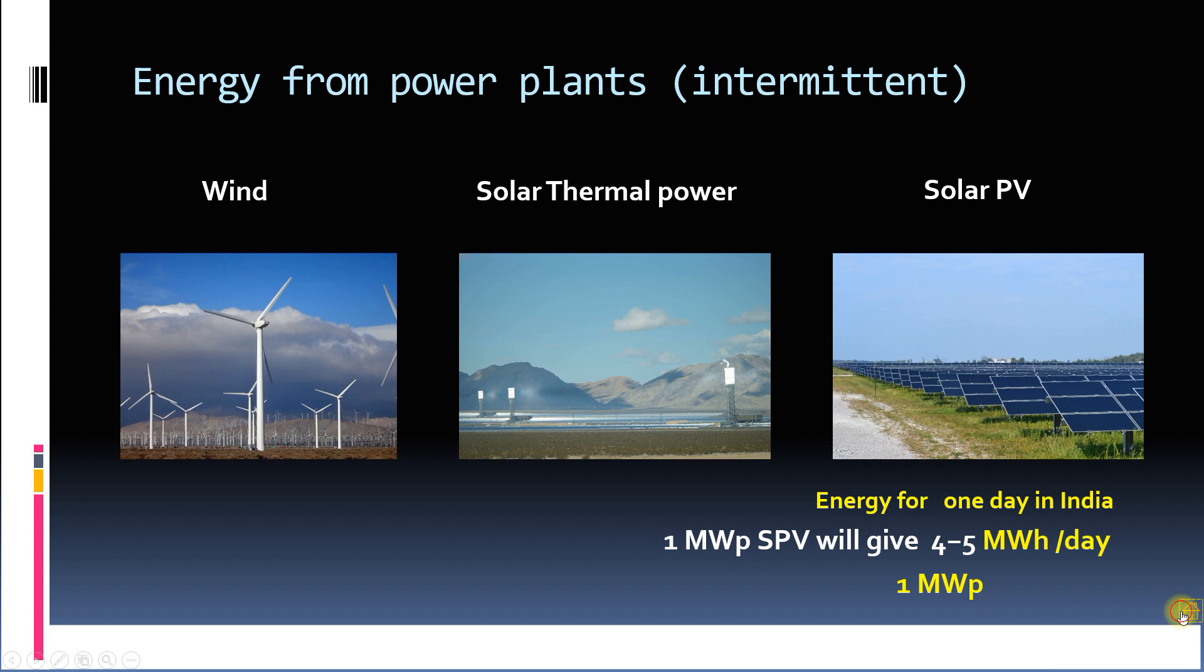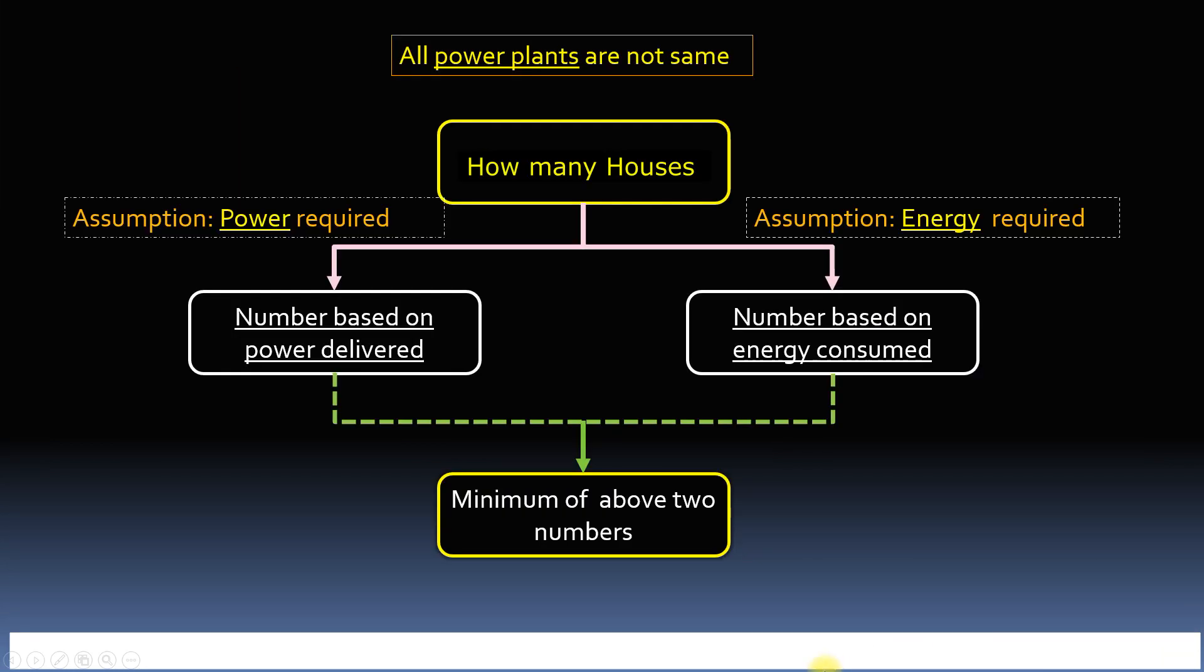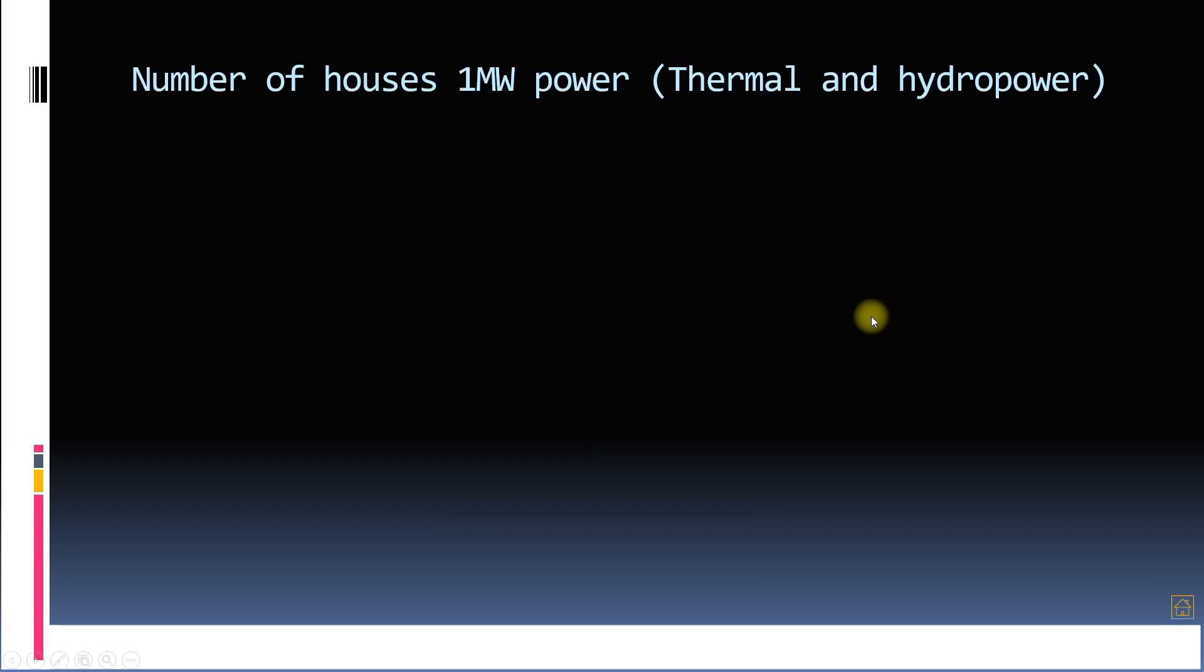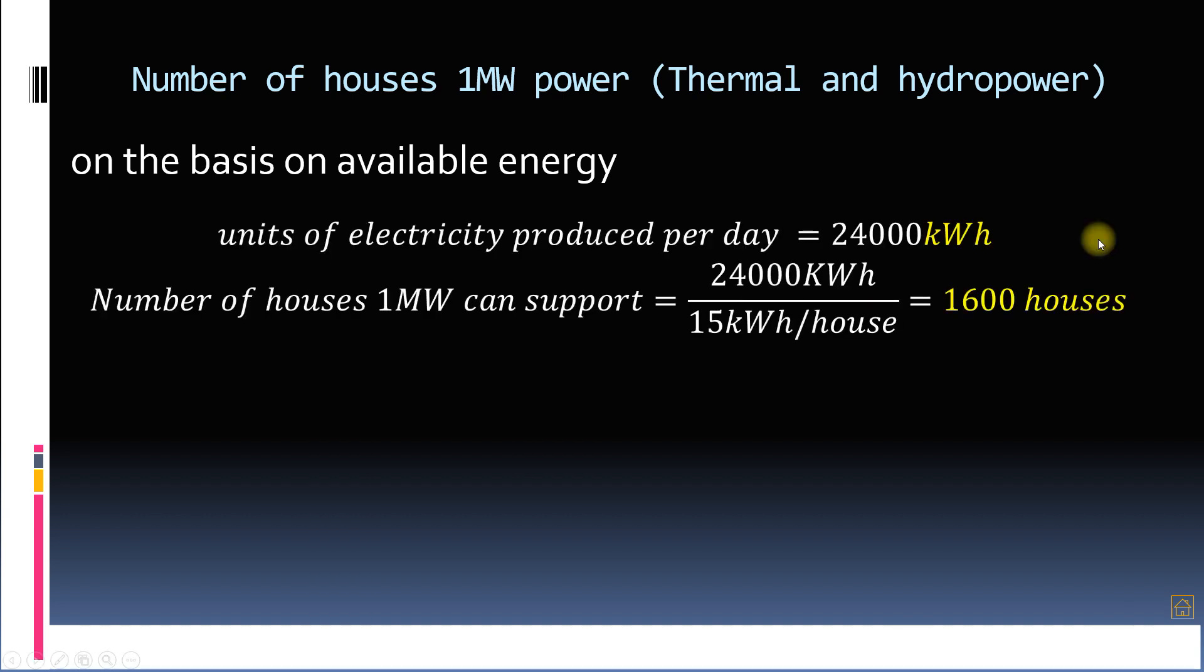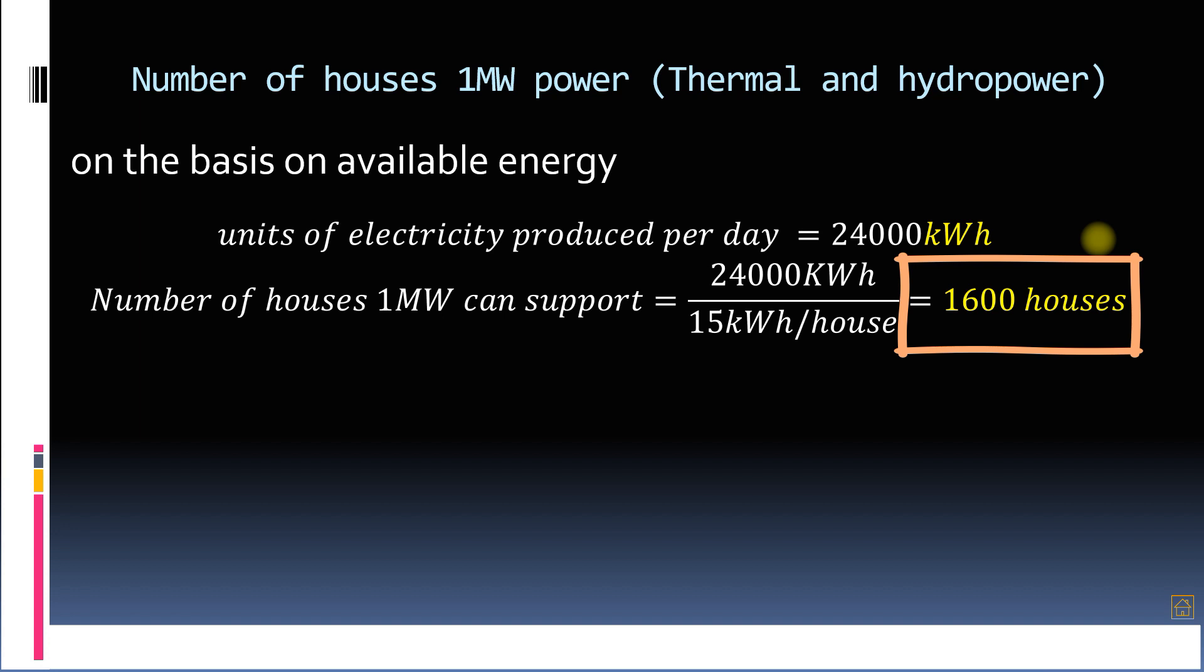Let's do the calculation now for the first type of power plants which can supply power continuously. On the basis of energy, for 1 megawatt continuous power plant we will get 24,000 kilowatt hours of energy per day. The energy consumed per house is 15 kilowatt hours. Therefore, we will get 24,000 kilowatt hours divided by 15 kilowatt hour per house. That is around 1600 houses. So 1600 houses can be supported by 1 megawatt continuous power plant on the basis of energy consumption.